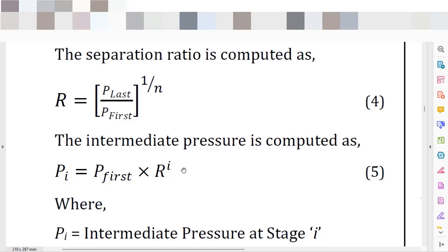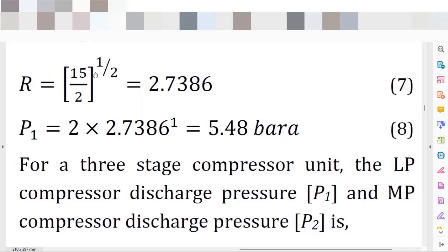To exemplify that, we can see the calculations performed in the article. In the e-book's case study, we have a discharge pressure condition of 15 bar A and an inlet condition of 2 bar A. So the global pressure ratio is 15 divided by 2, which gives 7.5 — dimensionless. Because we have two stages of compression, we take the square root of 7.5, which leads to 2.7386. The discharge pressure of the first stage is 2 bar A multiplied by 2.7386, giving 5.48 bar A.